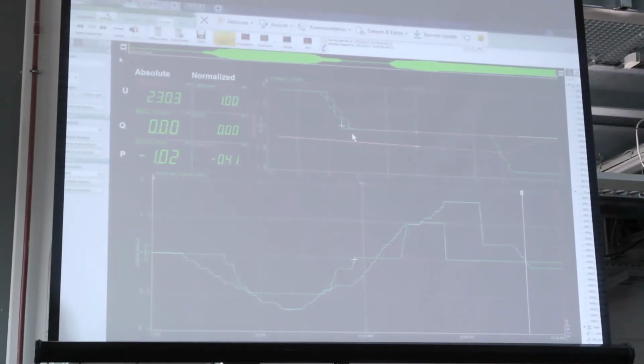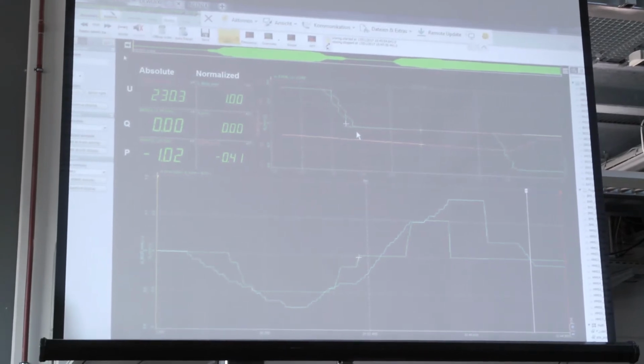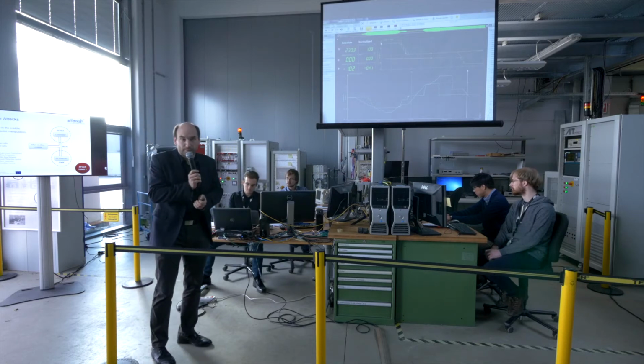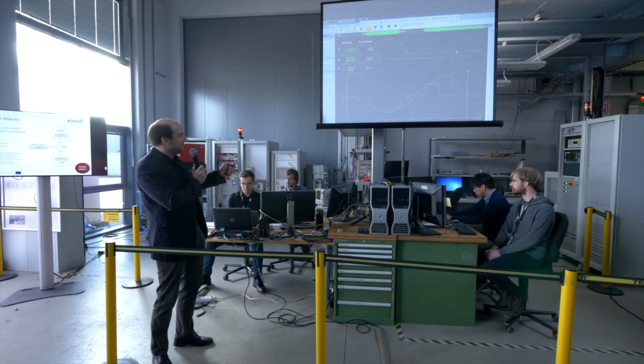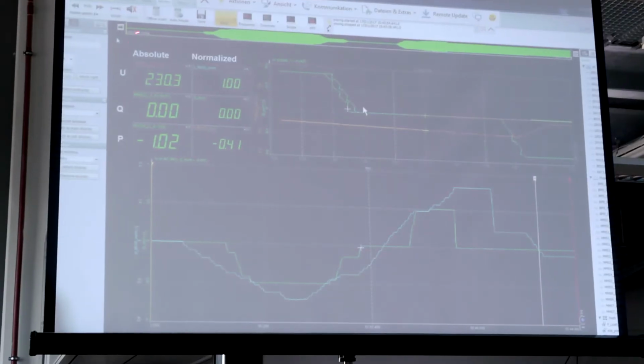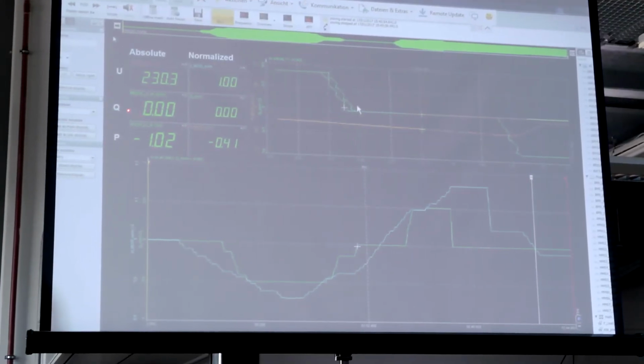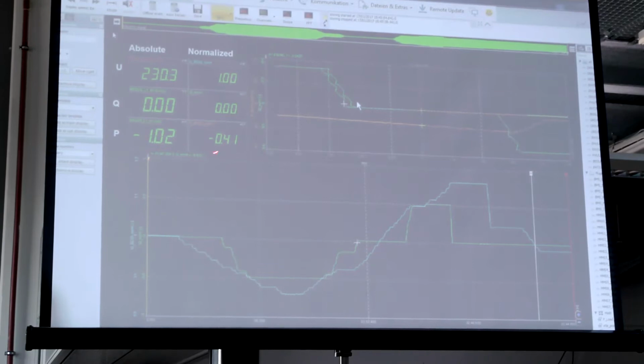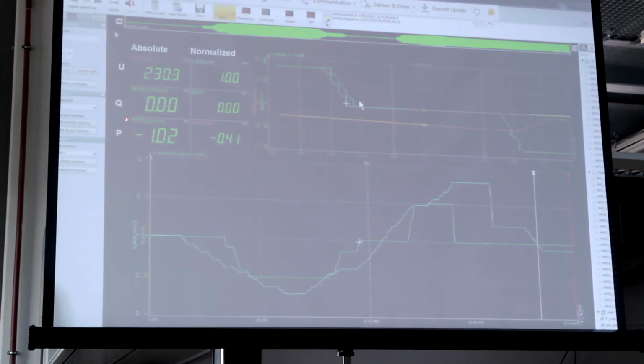And here we see the chart with the measurements from the real inverter, from this connection point. We'll see this chart more often today, so let's get organized here - we see absolute values. For example, active power is 1 kilowatt fed in by the inverter into the grid. It's negative because it counts like a load, so a negative load is a feeding. We have 230 volts, so everything is in a nice condition.